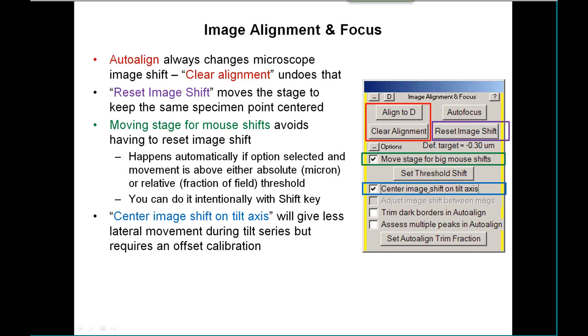Another feature is centering the image shift on the tilt axis, which is useful for allowing less lateral movement during a tilt series or during operations that tilt from one angle to another. It does require a calibration of the offset of the tilt axis from the optical axis, and during the demos you'll see how that's pretty easy to accomplish.